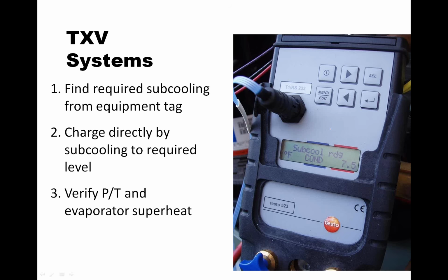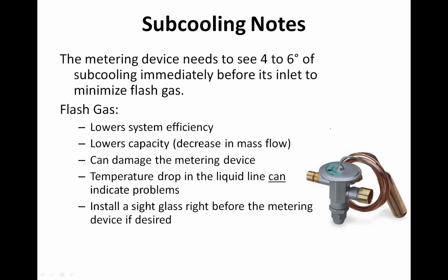So we always evaluate both sides of the system. Don't just assume because you have correct subcooling that your superheat's fine. You've got to look at both sides. For the TXV to operate properly, the metering device needs at least 4 to 6 degrees of subcooling immediately before its inlet. Now, as practice, I typically install a port on the liquid line right before it enters the TXV. That's just me. And what I can do there is I can go in the house, connect my pressure port there, connect my temperature port there, and I make sure that I still have subcooling before I enter the thermostatic expansion valve.